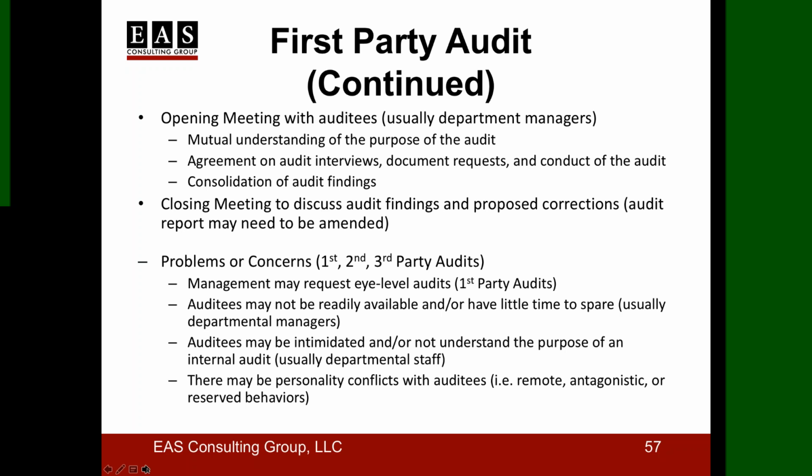management controls and management reviews. As I said, there's usually an opening meeting, usually with department managers and these different types of auditees. If you're looking at design controls, it's usually the design and development engineers and the managers. You're looking at the SOPs for design controls, and you're picking one or two design history files to audit.